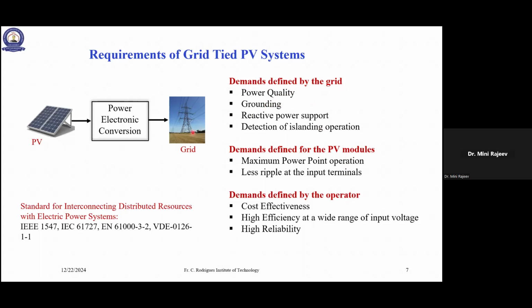For single phase grid, the neutral should be grounded as per standards. Then reactive power support. This will help again in peak demand. When the voltage sag occurs, if you provide reactive power support, you can bring it back. The voltage which was reduced, you can bring it back. So you can provide reactive power support. Then detection of islanding operation.